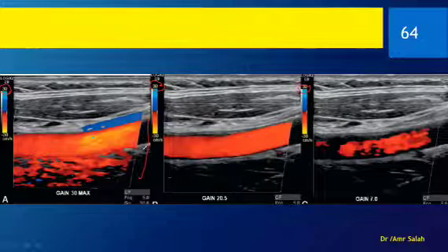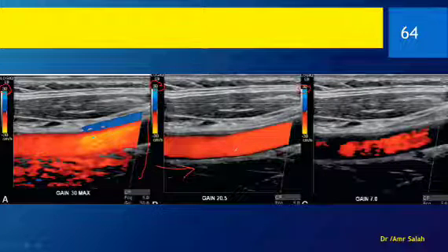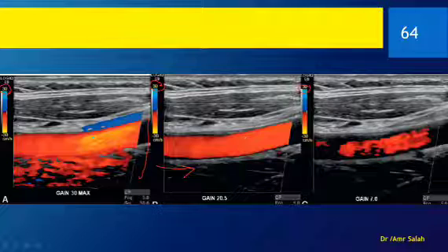So what to do? We decrease the gain gradually until it just fills the blood vessel, and that will be it. Then it is okay and it is very good, and we can furthermore control the grades of the color inside with the PRF, as we just discussed earlier, according to the velocity, of course, in the blood vessel.